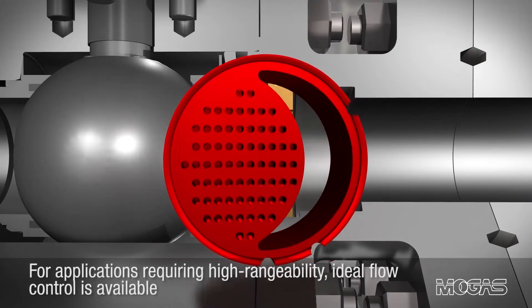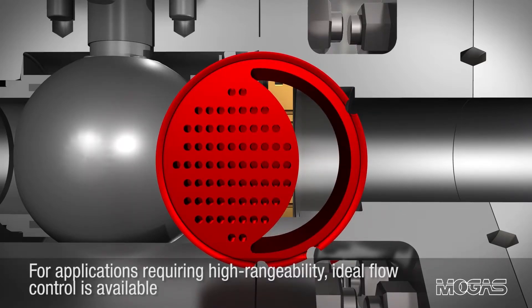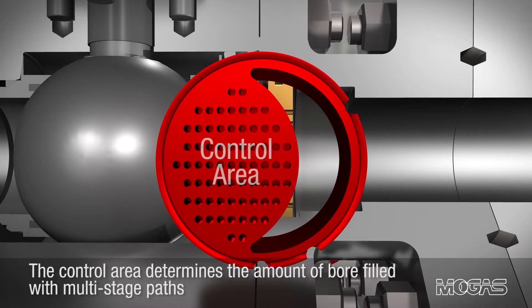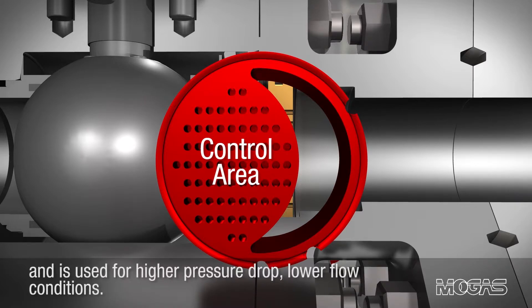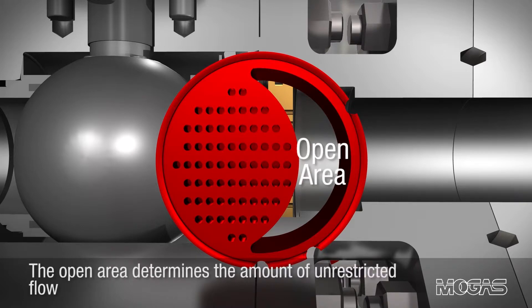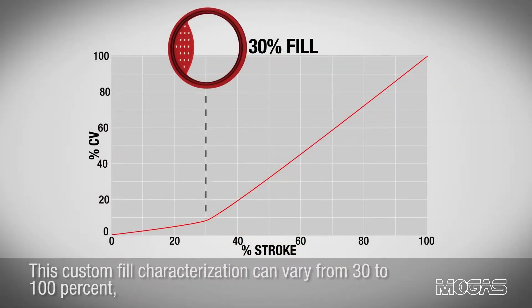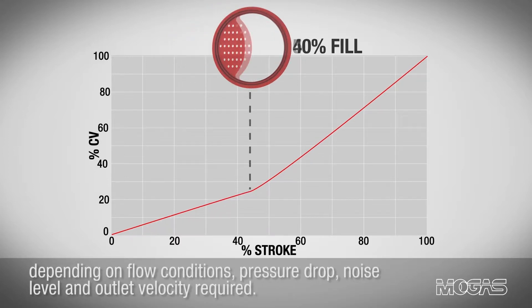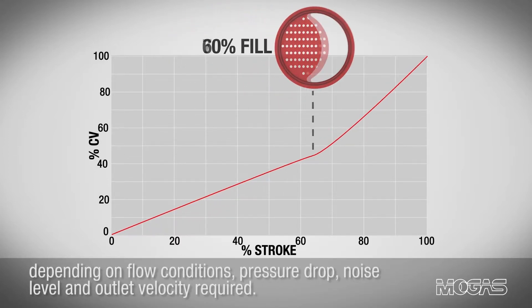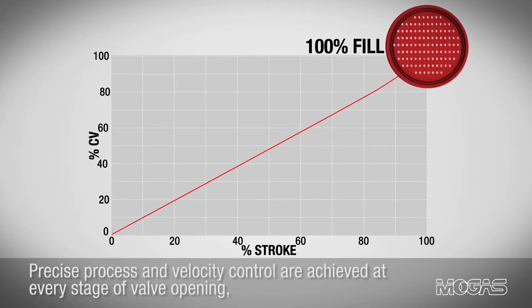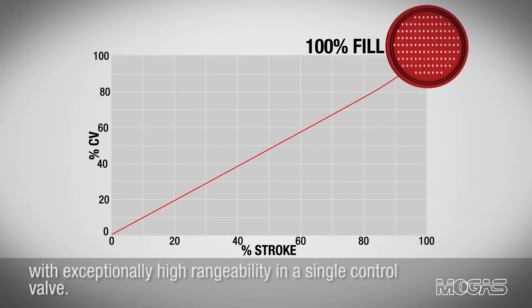For applications requiring high rangeability, ideal flow control is available by varying the combination of control area and open area within the trim. The control area determines the amount of bore filled with multi-stage paths and is used for higher pressure drop, lower flow conditions. The open area determines the amount of unrestricted flow and is used for lower pressure drop, higher flow conditions. This custom fill characterization can vary from 30 to 100 percent depending on flow conditions, pressure drop, noise level, and outlet velocity required. Precise process and velocity control are achieved at every stage of valve opening with exceptionally high rangeability in a single control valve.